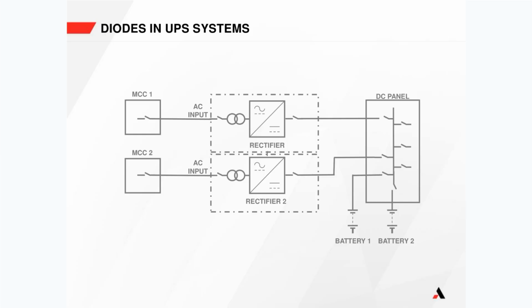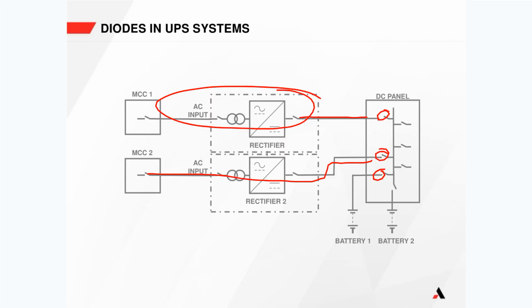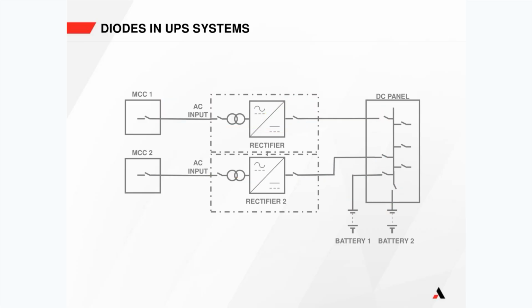You have one charger at the top that's connected to a DC panel through a breaker. You have another charger connected to the same DC panel through a breaker. And then we have two batteries through their own breakers connected to that DC panel. That means we can remove any piece of this system, and the DC panel will continue to remain powered. It is the most redundant, easy to maintain system out there.